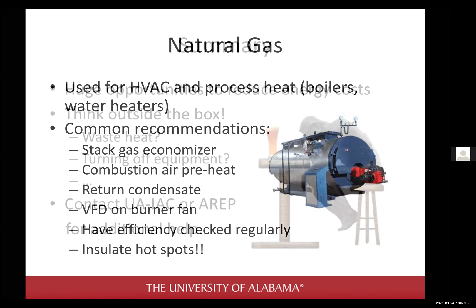Other ways to save energy: variable frequency drives on the burner fan can save electricity and natural gas. Also, if you can insulate any hotspots on the boiler or your steam system, you'll save on natural gas usage. I won't spend too much time on this since it involves combustion analysis, but if you can get somebody to analyze the combustion on your water heater or natural gas system, it might be worthwhile. You could be doing things incredibly inefficiently, or you might be doing really well, but it's nice to know either way.